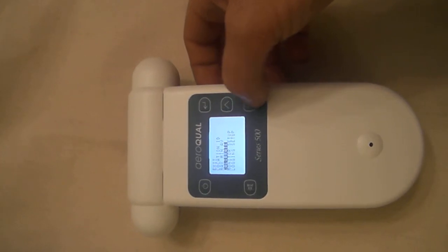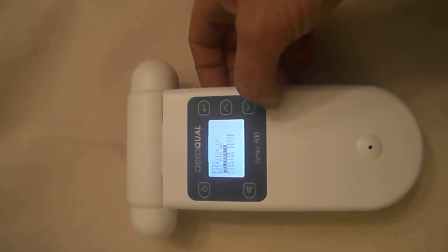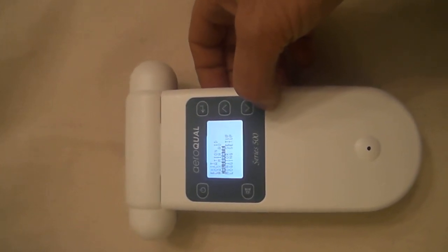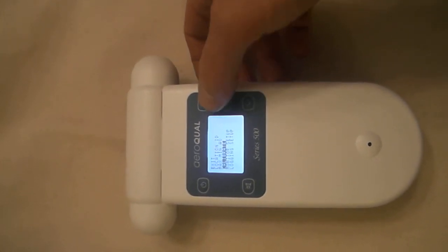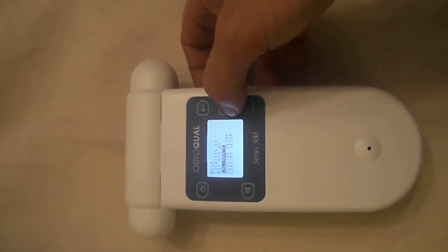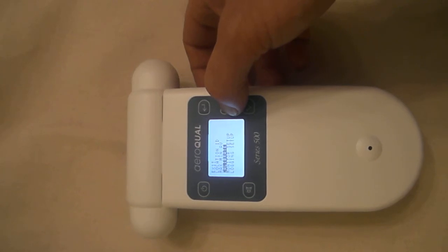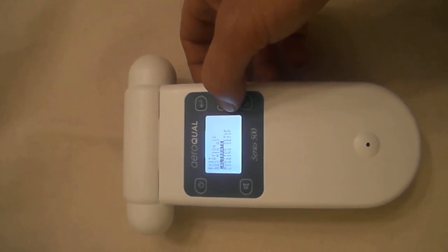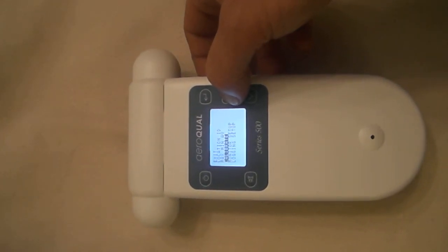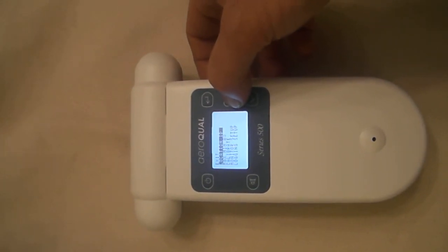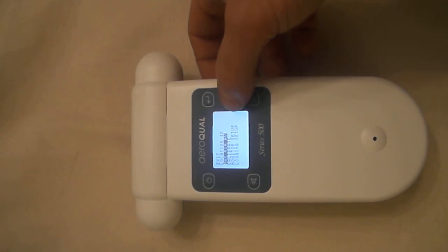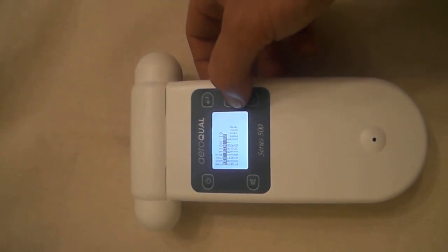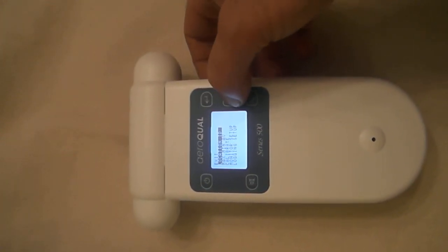Calibration, if you have the optional calibrator, you can calibrate the monitor right here with the head. You don't need a separate calibration base and the min-max and average can be set right here.